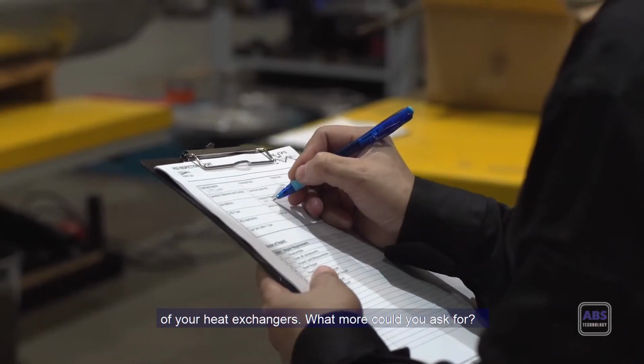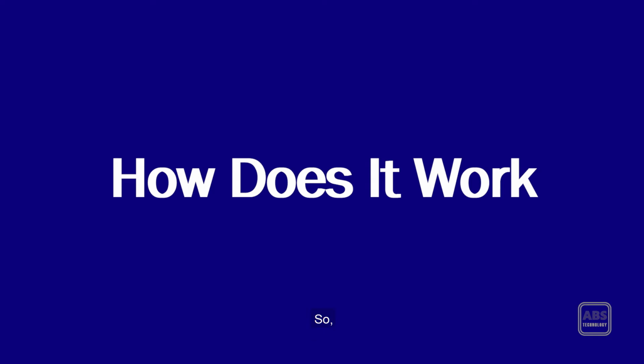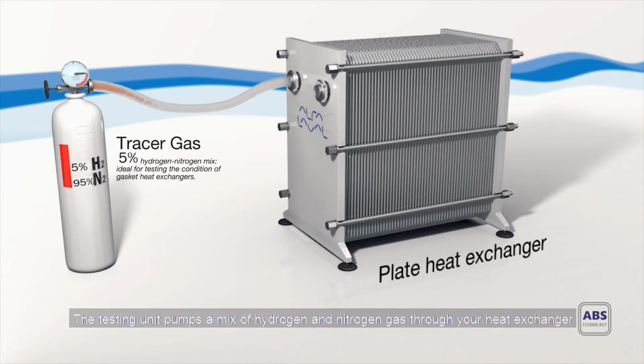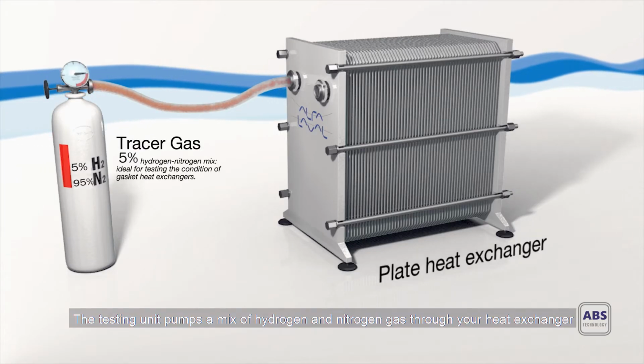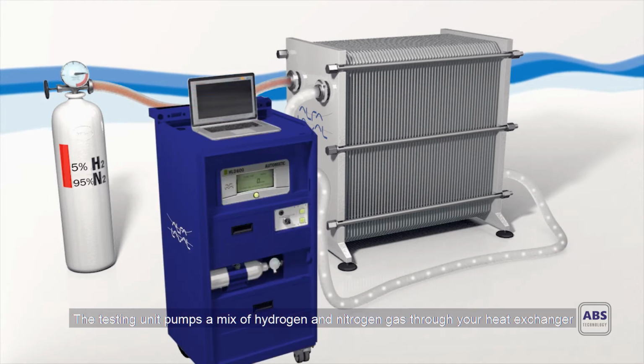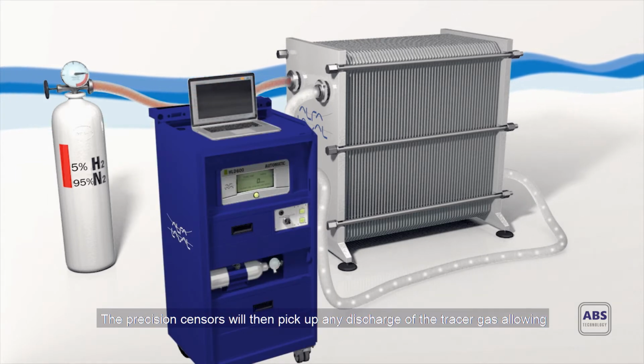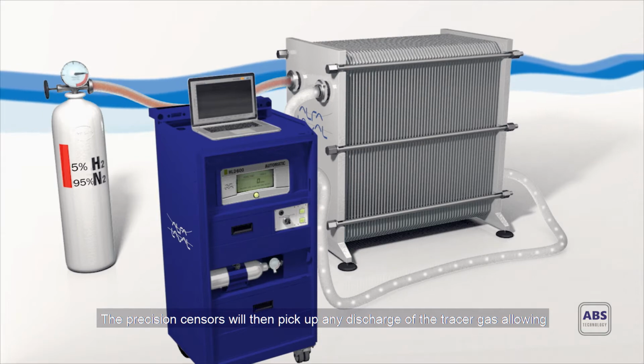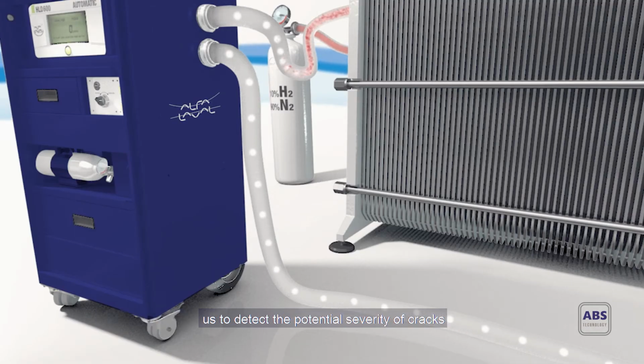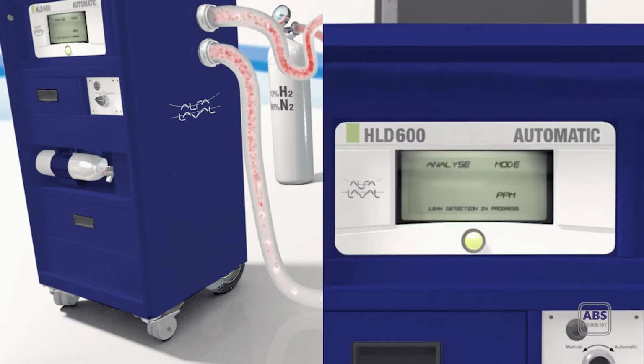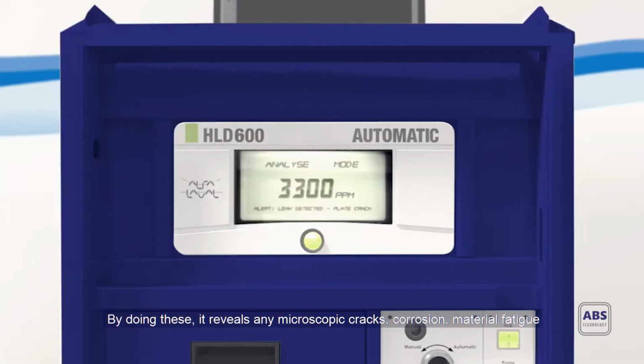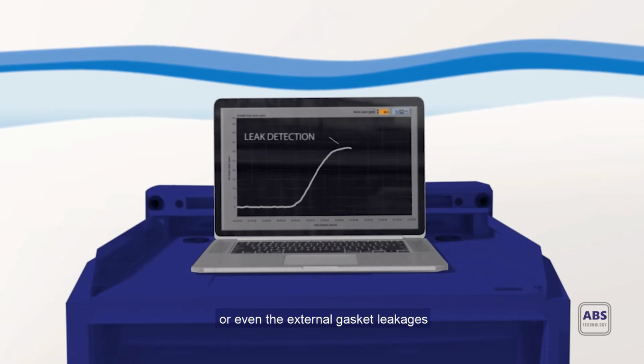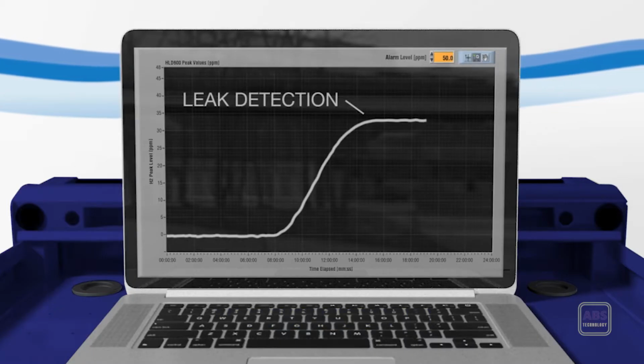What more could you ask for? So how does it work? The testing unit pumps a mix of hydrogen and nitrogen gas through your heat exchanger. Precision sensors then pick up any discharge of the tracer gas, allowing us to detect the potential severity of cracks. By doing this, it reveals any microscopic cracks, corrosion, material fatigue, or even external gasket leakages.